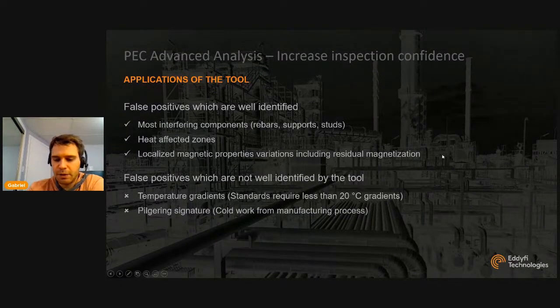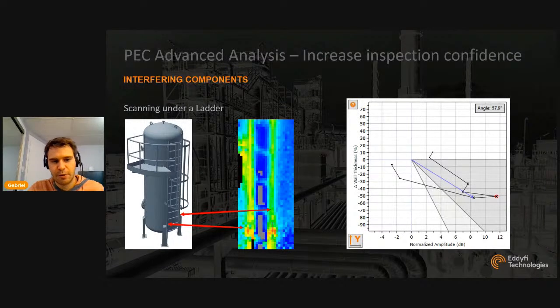The tool is not a silver bullet. It works on many use cases of false positive, but not all of them. So it's going to work for most cases of interfering components that could be rebars inside concrete fireproofing, pipe supports, studs in fireproofing, a surrounding component that's surrounding the one you're inspecting and that's affecting the PEC signals. It works well in heat affected zone and localized magnetic property variations, including residual magnetization. It does not work well on temperature gradients, but the standards require you to inspect only components where you've got less than 20 Celsius gradient between the calibration and inspection area. And it's not going to work on pilgering signature, but we'll go over all of those examples very quickly now.